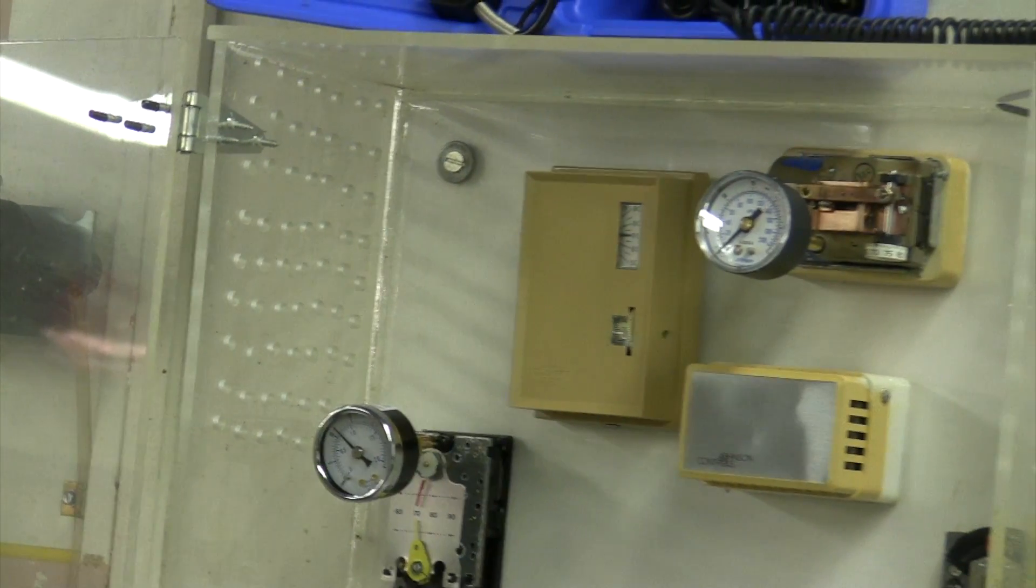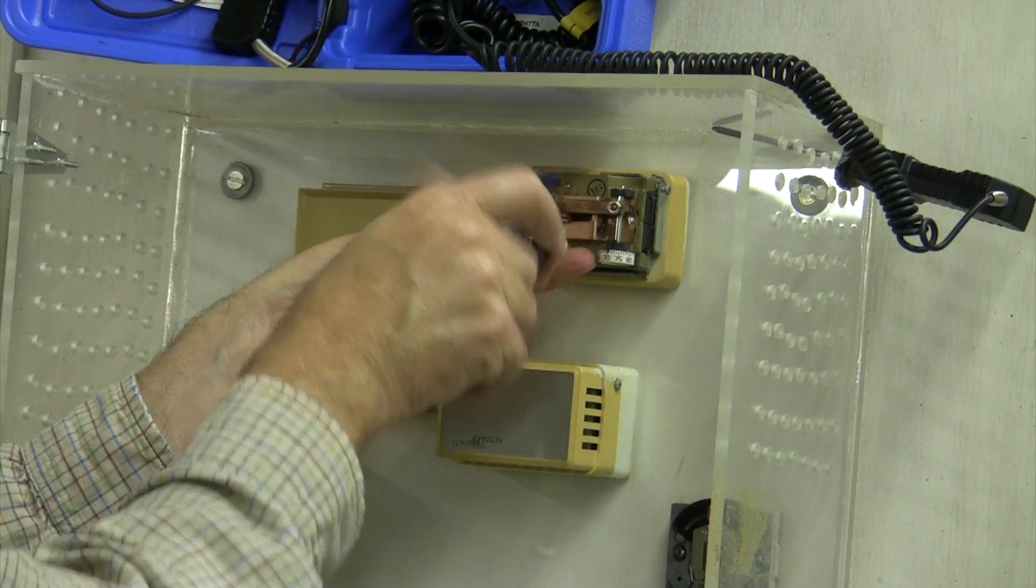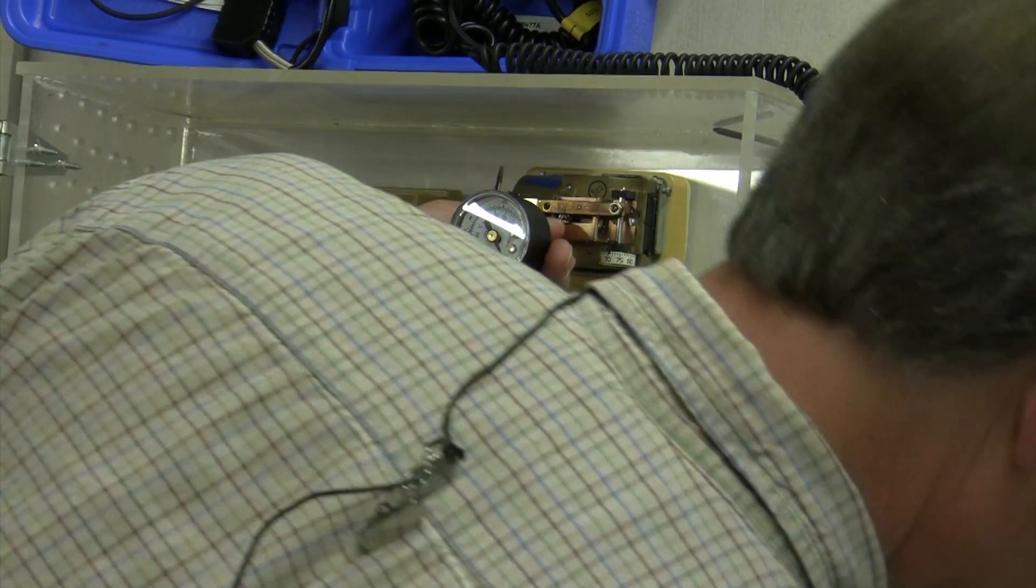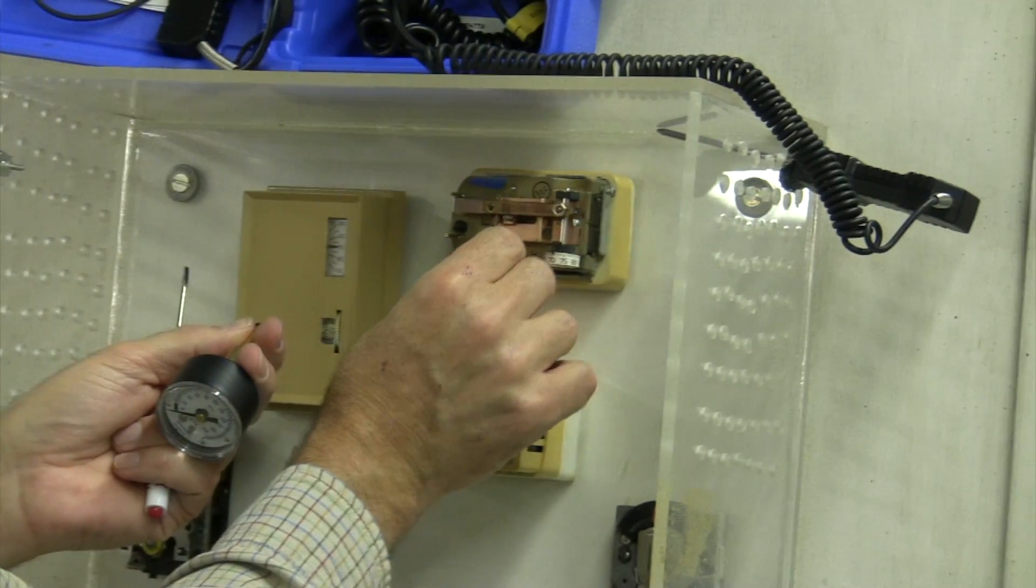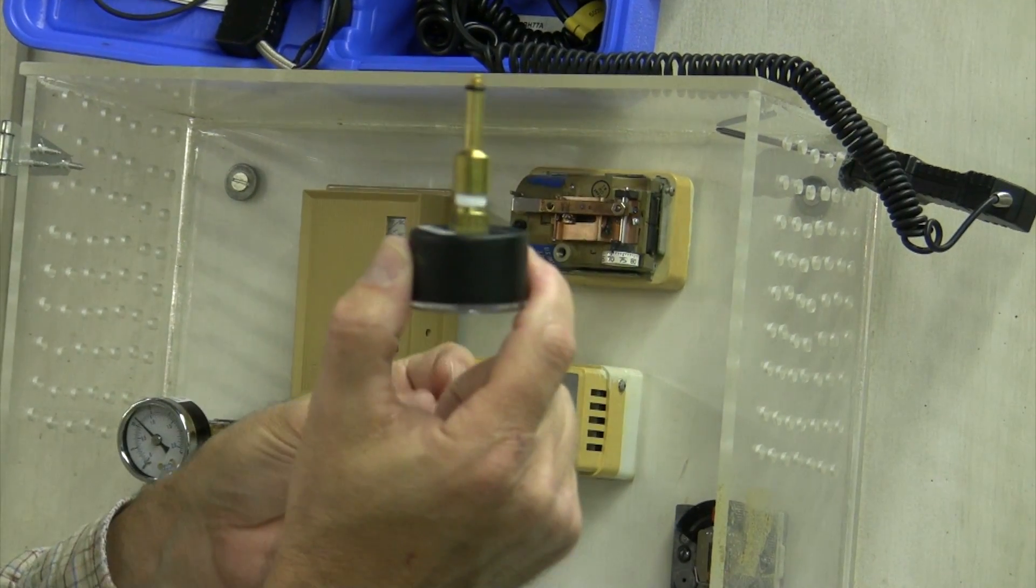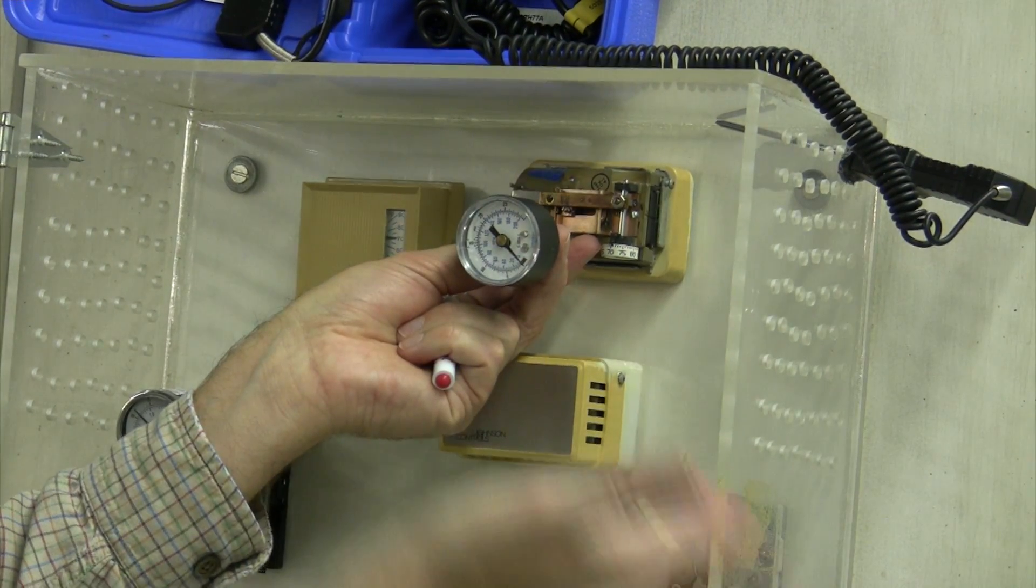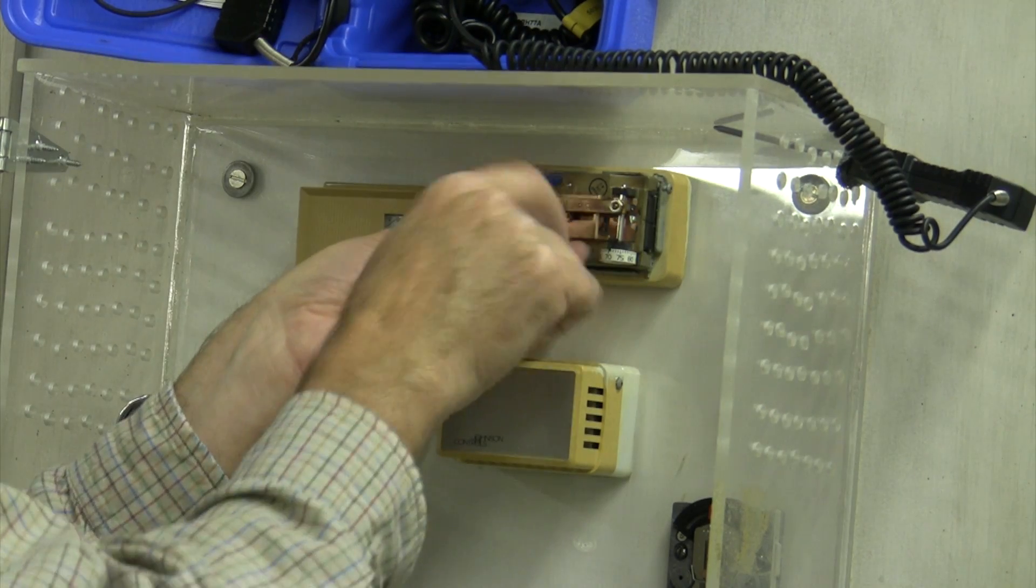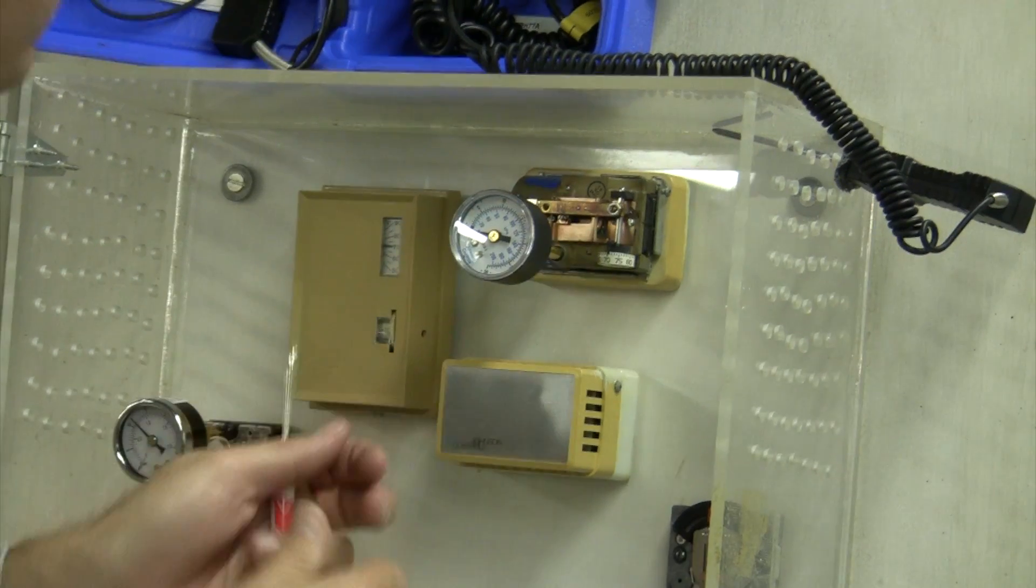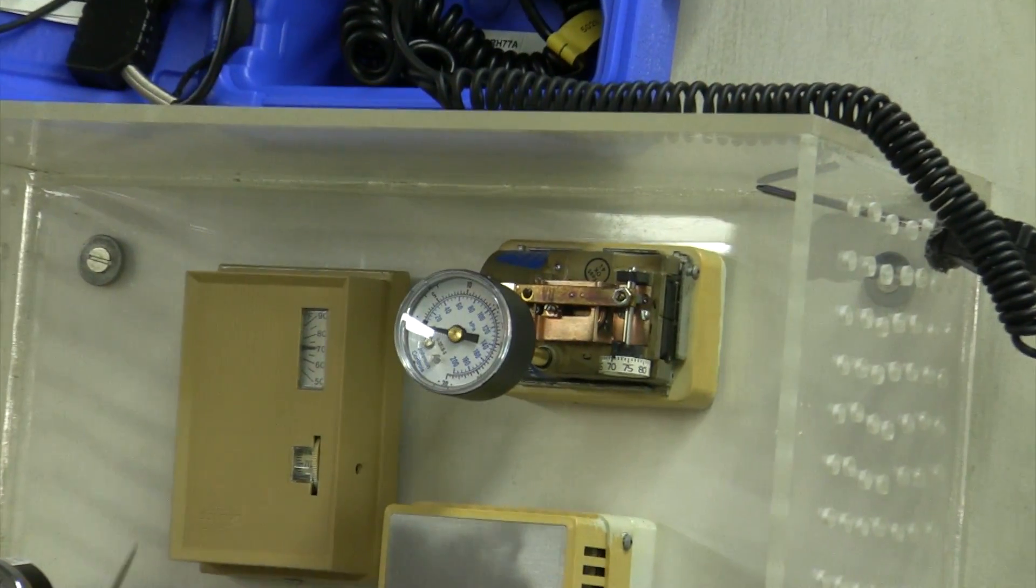Let's take a look at the Johnson Controls stat. I've already inserted a test gauge. This has a port right here that you can put a needle gauge in, but I really like this little adapter. You pull this little plug out, screw this in, and it's so much easier than working with that needle gauge. Alright, I've got my temperature dialed in, and obviously I'm way off calibration. Let's see if we can tweak this.